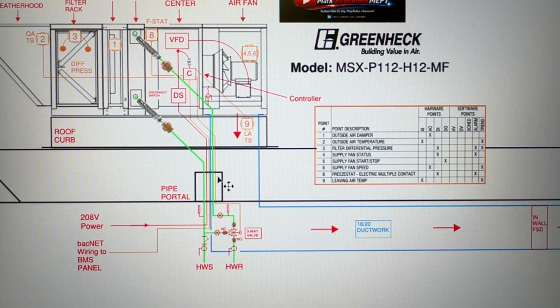So this pipe portal here is up on the roof as well. It sits close by to where this roof curb is, and what that'll do is allow us to have an access point to run our piping up through the roof and connect over to the coil. It also allows access for our electrical contractor, power contractor, and our controls contractor to get their utilities over to the unit as well.